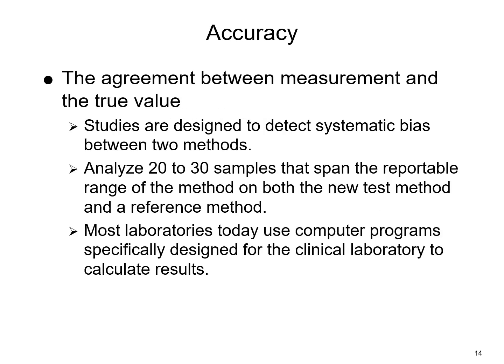So when we talk about a laboratory determining accuracy, or even a manufacturer determining accuracy of a test, we're basically saying, how accurate is this test? How close are we getting to the actual true value of whatever we're looking for? So there are studies that are designed that will detect any sort of systemic bias between different methods. So in other words, if you're doing a urine test by manual dip versus an automated dip, we've got to compare to make sure that we're getting consistent results, that we are accurate no matter whether we manually did it or whether the machine reads it.